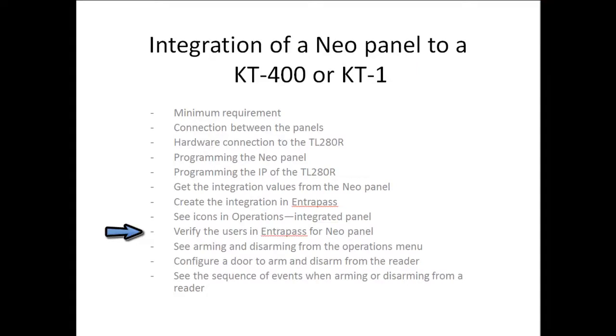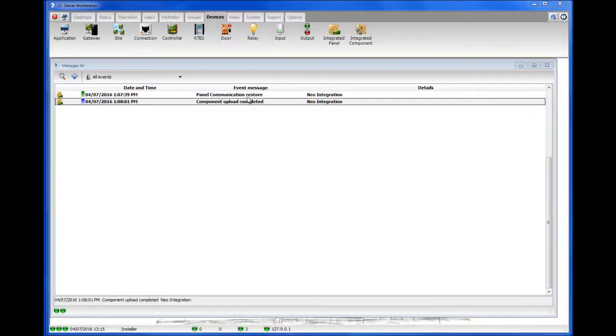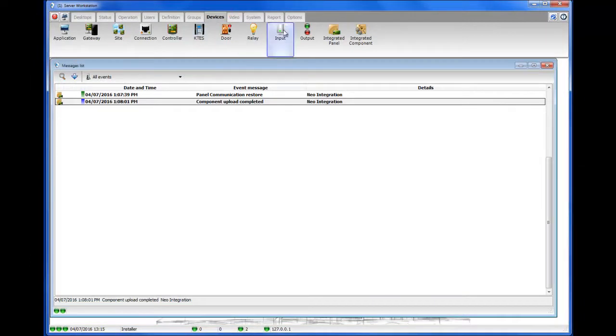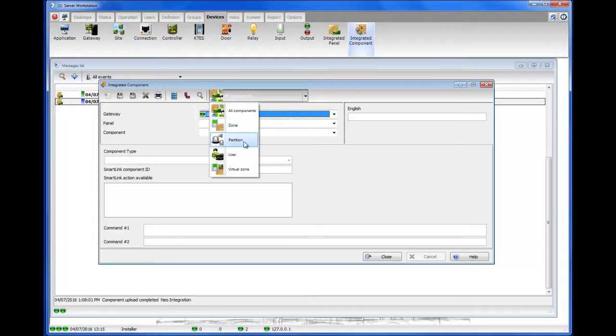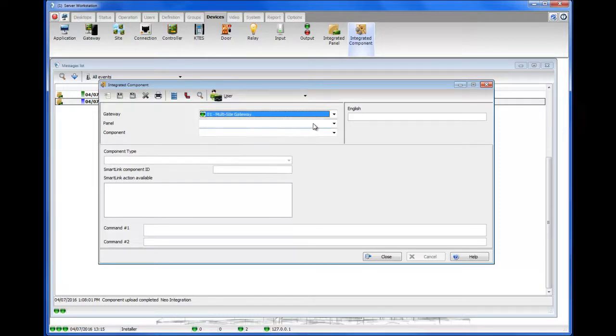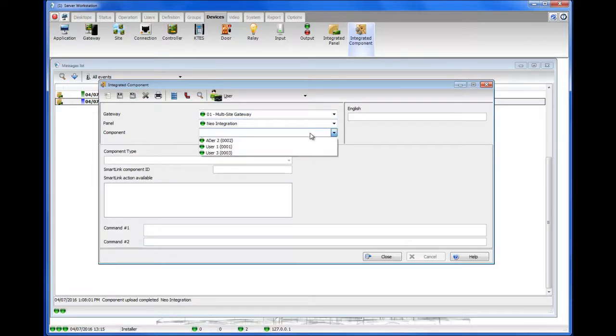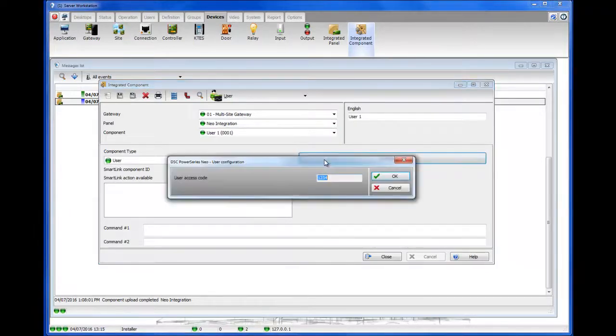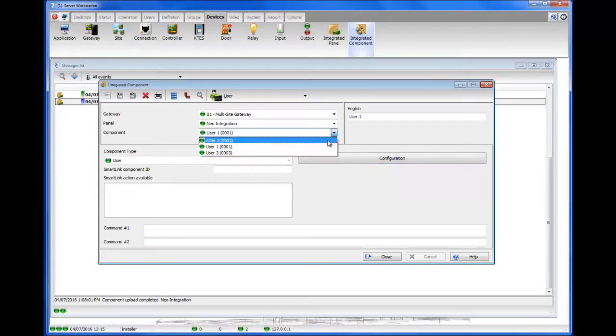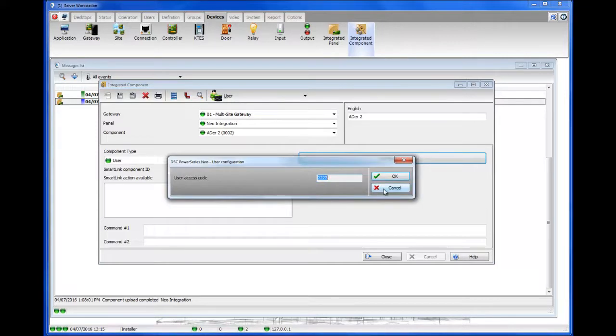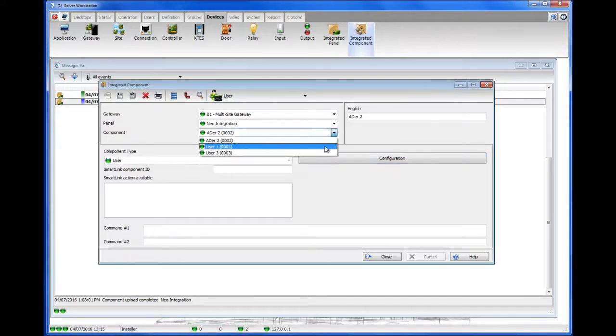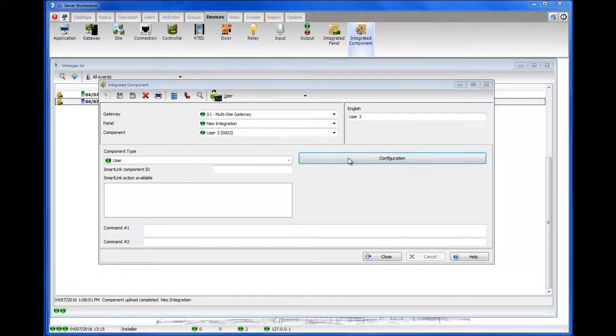Next, we'll want to verify the users in EntraPass for the NeoPanel. Go to Devices, Integrated Component. We can select to see only users — this will make it easier. Select user one and go to the configuration. You can see that it already uploaded the information about the user. If we check user two, his code is already in there too. And if we check user three, his code is also in there.